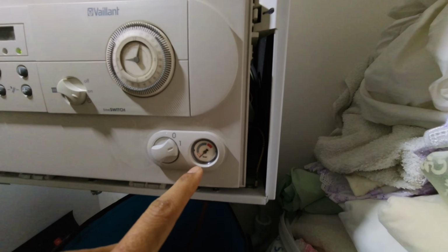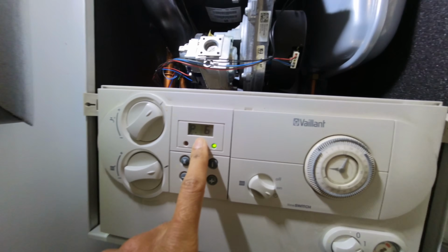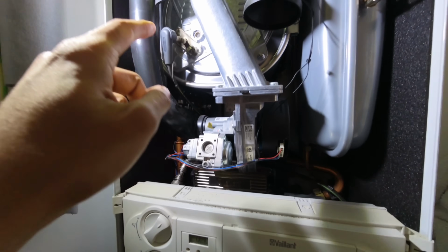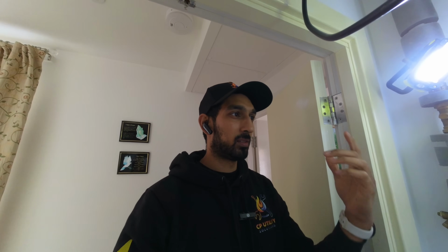We've drained the boiler out, so it's obviously showing 0 on the analog gauge, but we've still got 0.7 bar on there. I've got another pressure sensor on me, but the customer's on a bit of a budget, so I'm going to see if I can clean that out. Hopefully I can just clean it and get it to work, if not I'll see what I can do. They're not that expensive, but if it needs changing, it needs changing. Let's see what we can do.